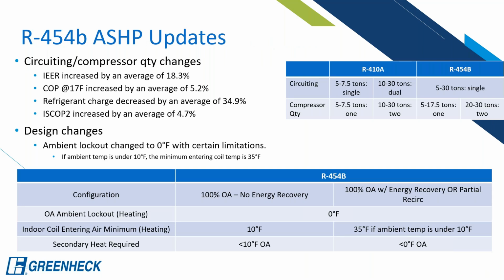So in the redesign to R454B, we've changed the circuiting and compressor quantity to basically make this thing more efficient. This helps with our ratings with the DOE, but overall, it's a more efficient design than what it was. The IEER, COP, and ISCOP2 have all increased. And those design changes come with an amazing ambient lockout of 0 degrees with certain limitations. It's important to understand that if your unit does not have energy recovery and the outdoor air temperature goes below 10 degrees, you will need secondary heat to make that work. Now, in our market, most of the time we're using energy recovery, so for the most part, you're never gonna be below 10 degrees with an energy recovery system in there. But again, we can always do backup and secondary supplemental heat.